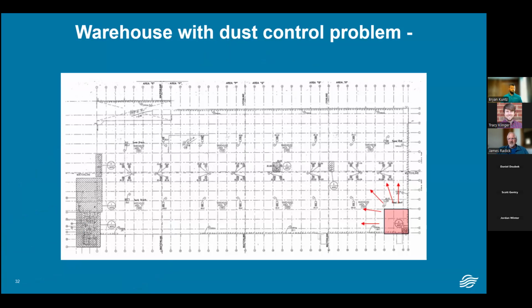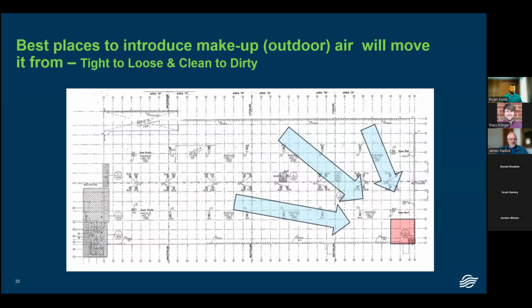But getting back to that building, warehouse with dust control problems. How did we address it? Okay, we've got this view showing the nasty area with the exhaust in the corner. Let's go to the next slide, please. We did it by looking at the exhaust that was leaving the building, infiltration air. We calculated an infiltration rate based on construction, etc.